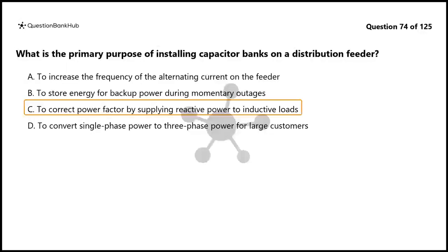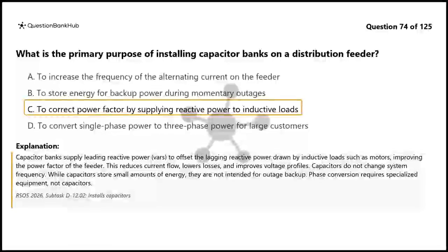The correct answer is C. Capacitor banks supply leading reactive power, VARs, to offset the lagging reactive power drawn by inductive loads such as motors, improving the power factor of the feeder. This reduces current flow, lowers losses, and improves voltage profiles. Capacitors do not change system frequency. While capacitors store small amounts of energy, they are not intended for outage backup. Phase conversion requires specialized equipment, not capacitors.